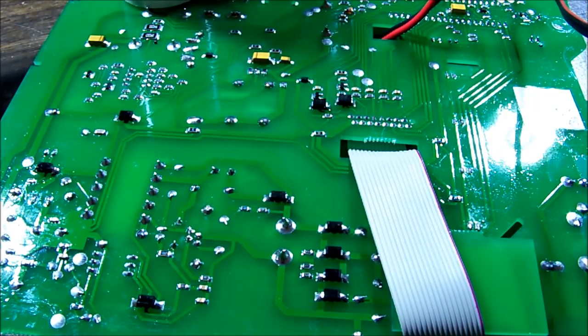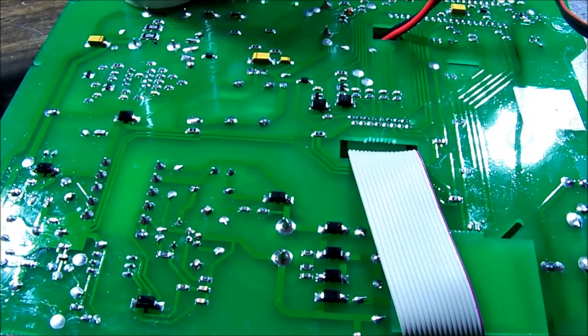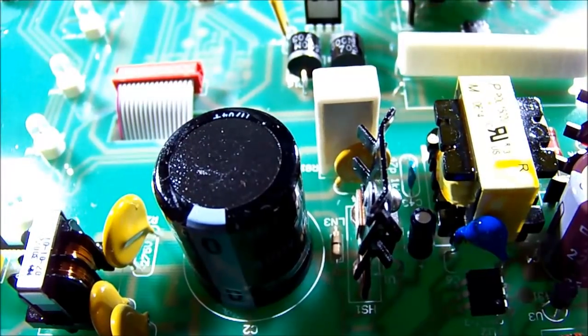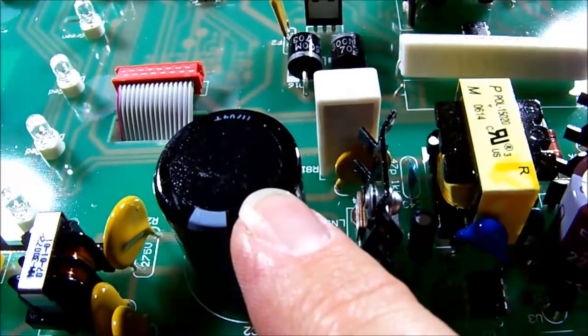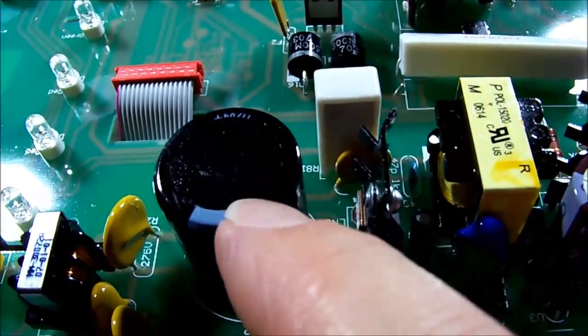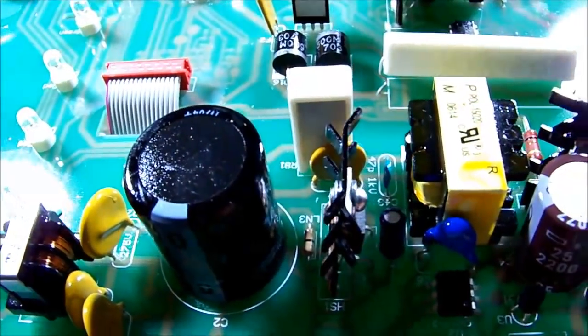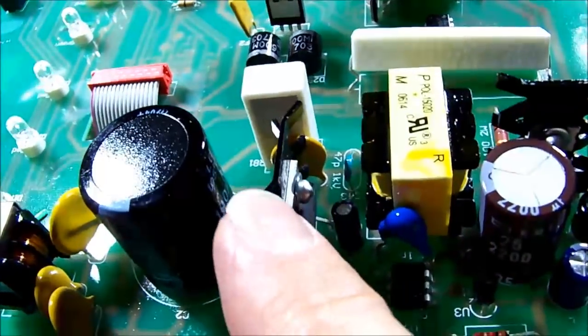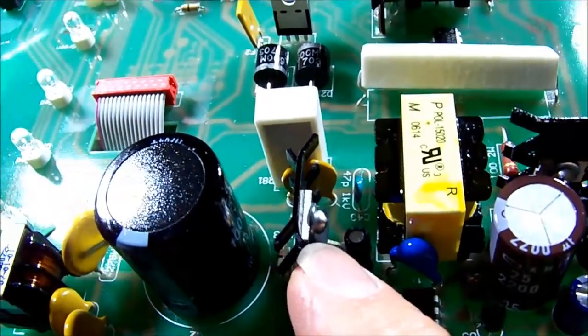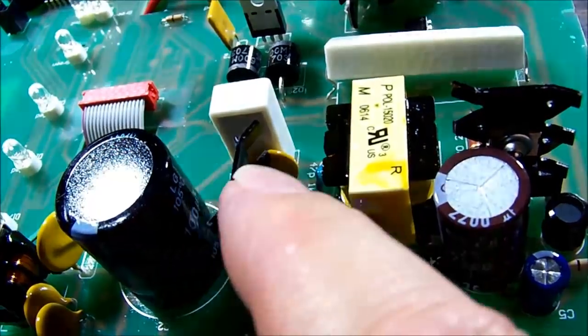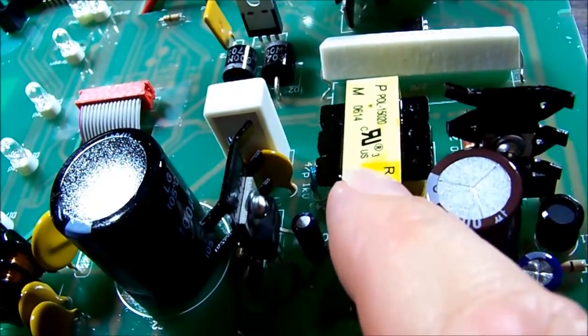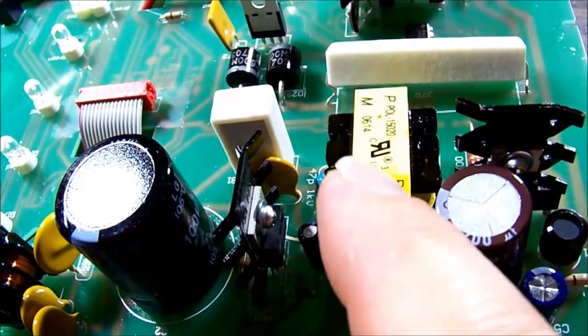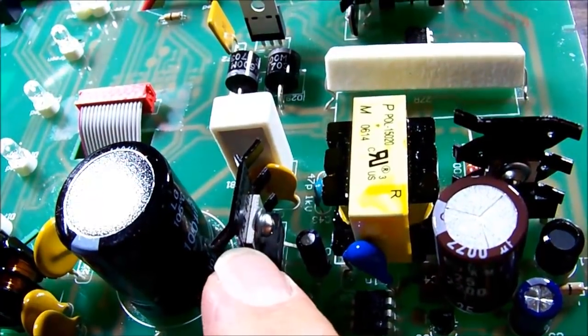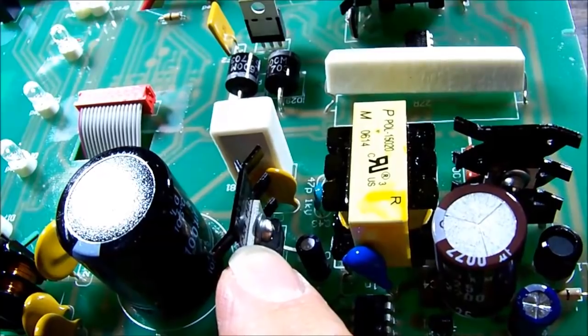So why do we have such a low resistance across the secondary of the input? Probably not this, I have yet to see one of those fail. It's probably our switching input controller. There's really nothing much across that, because all it is, is switching across the winding of that transformer, which shouldn't be measuring that until this switch is on, so it could have an internal short.